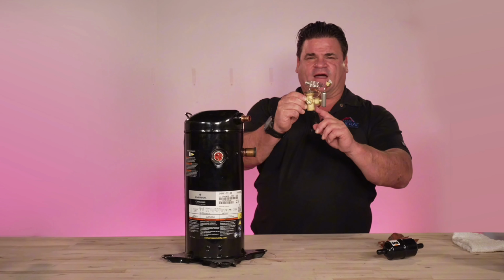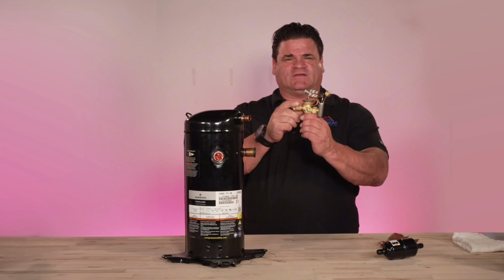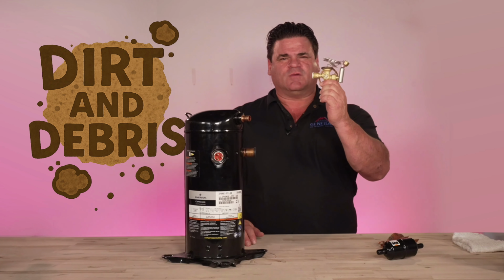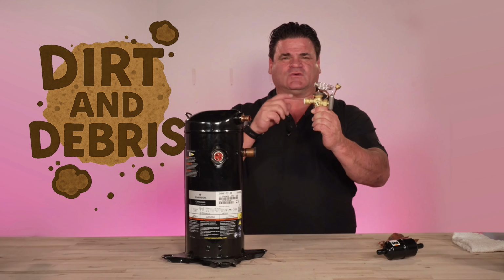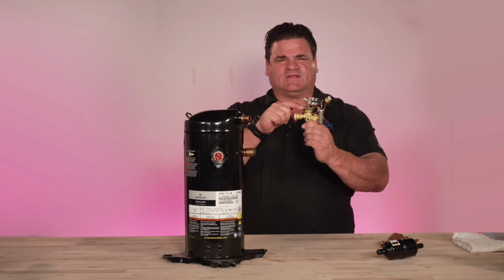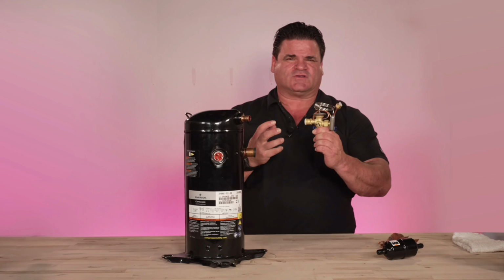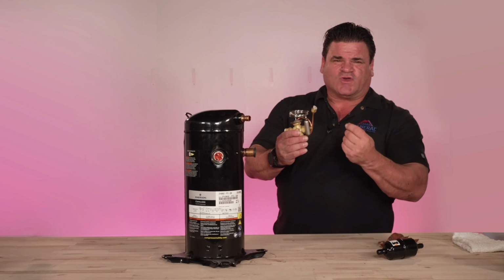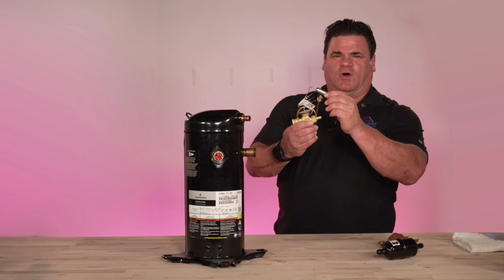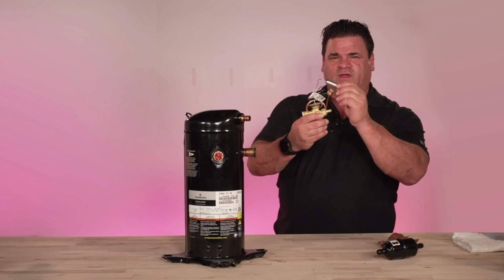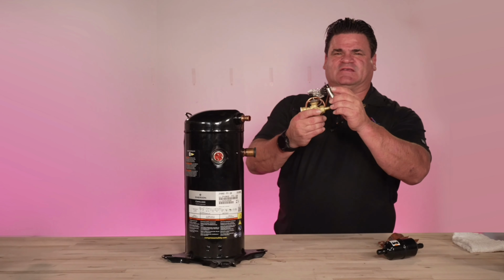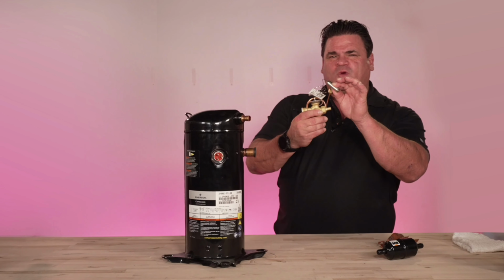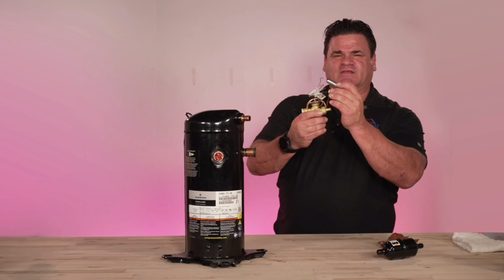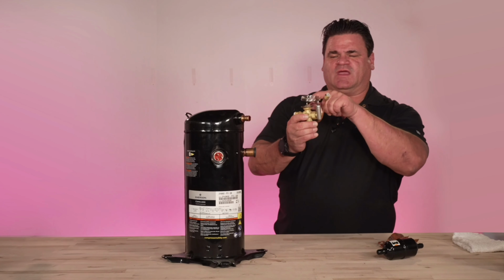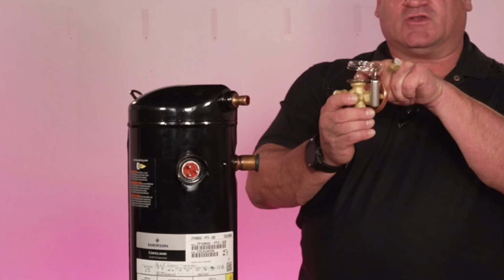Now, this can get fouled up. How can this get fouled up? Well, there's several ways. One of the biggest ways is dirt and debris getting into this. Could get into this or your capillary tubes, but for fouling the TXV, it gets into here, causes clogs and backups and restricted flow, things like that. This bulb, if this bulb is not placed in the correct area, if it's not connected at all, it's not going to be able to do the proper measurement to know what demand is being placed on the system to communicate to this TXV how much refrigerant to let in.